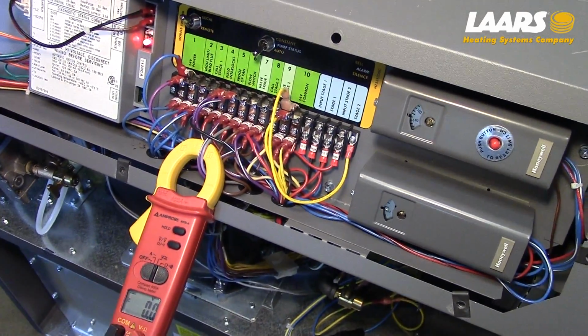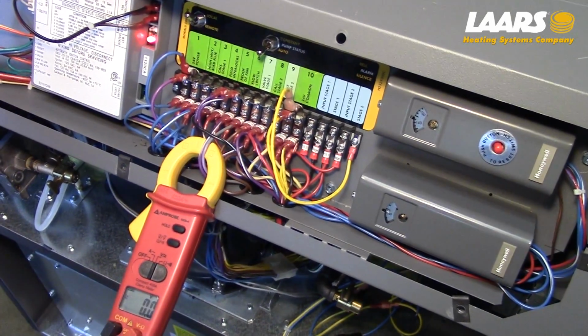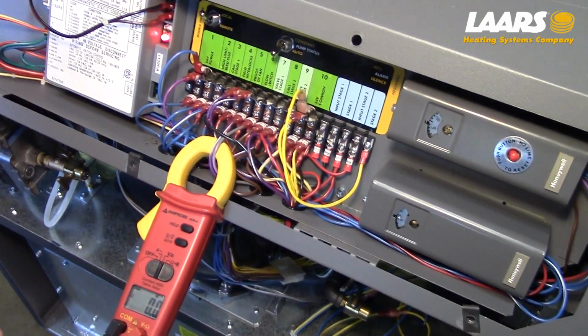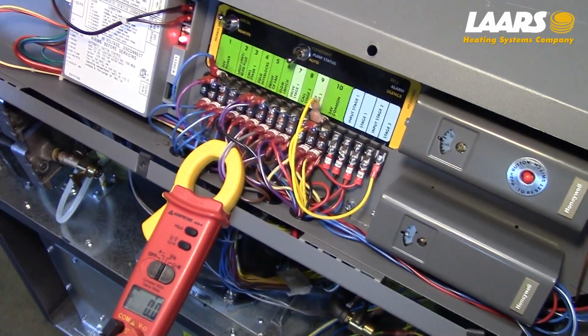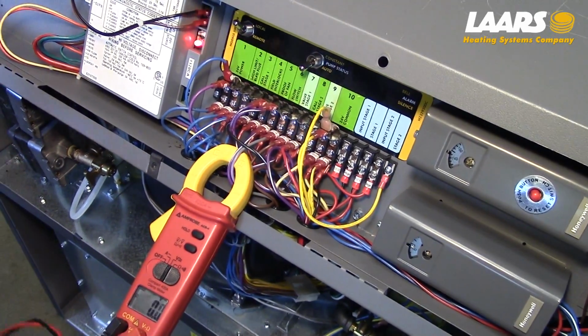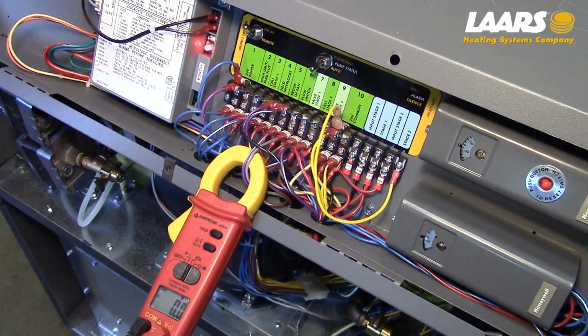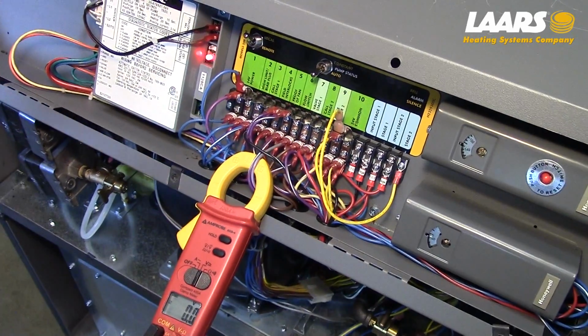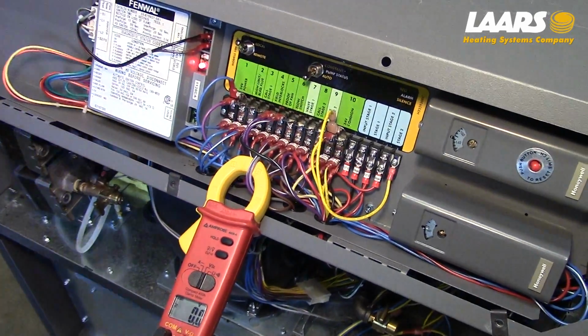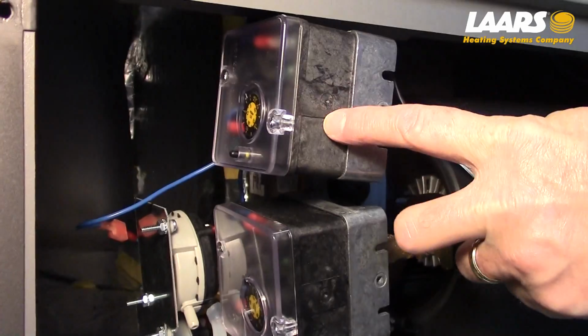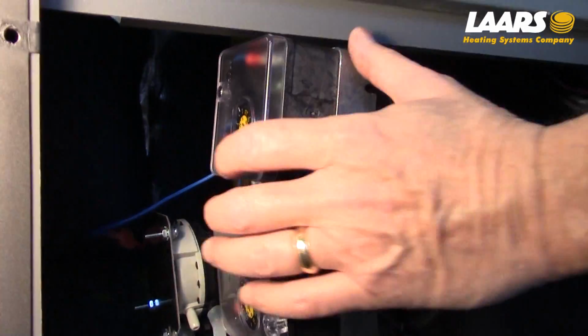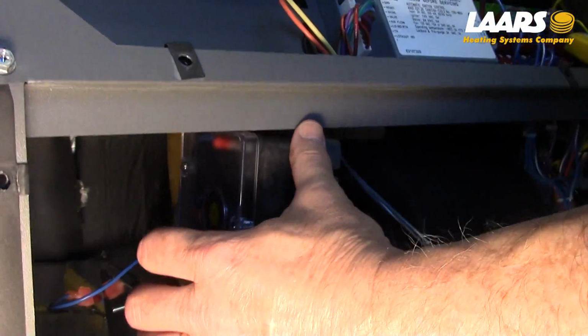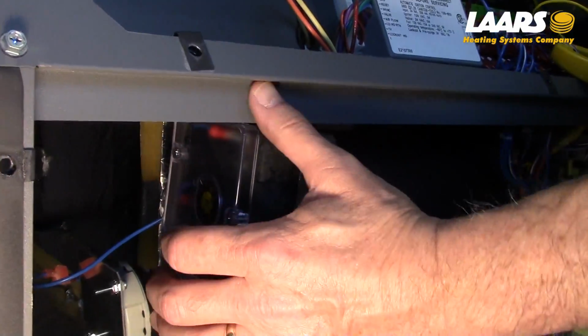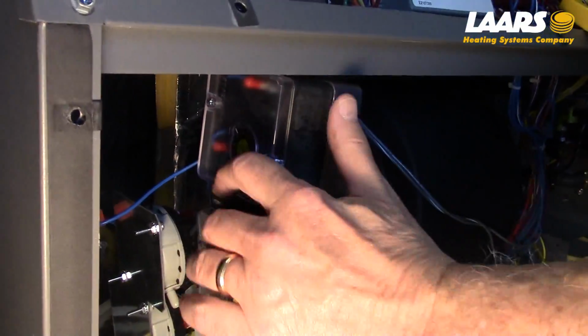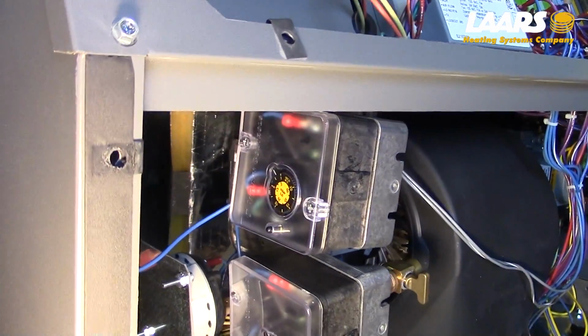So that's telling me that the high limit blocked flue, something there is open or something else in the safety circuit. So if you have what's called CSD1 controls, a low water cutoff, high gas pressure, low gas pressure, double check those. Okay, on startup that will be tripped on a CSD1 boiler. So in this case I have a high gas pressure switch and a low gas pressure switch. I'm going to reset my gas pressure switches. Okay, and just make sure that I have gas to the boiler.